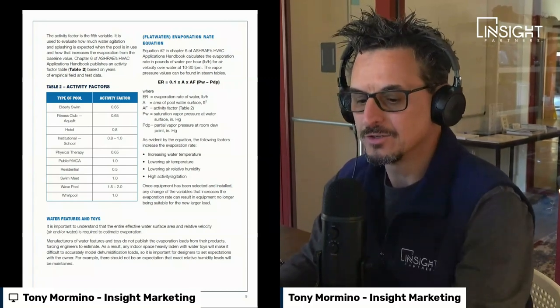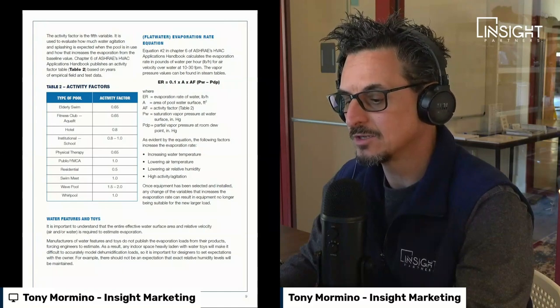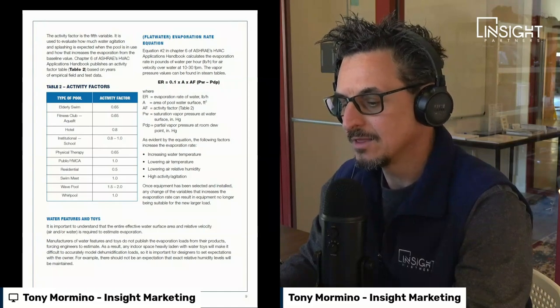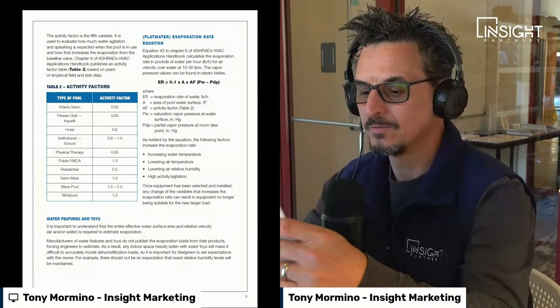It is important to understand that the entire effective water surface area and relative velocity — air and/or water — is required to estimate evaporation for water features and toys. Manufacturers of water features and toys do not publish evaporation loads for their products, forcing engineers to estimate. As a result, any indoor space heavily laden with water toys will make it difficult to accurately model dehumidification loads, so it is important for designers to set expectations with owners — for example, there should not be an expectation that relative humidity levels will be maintained.